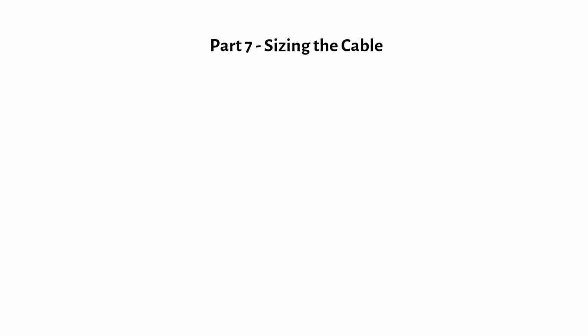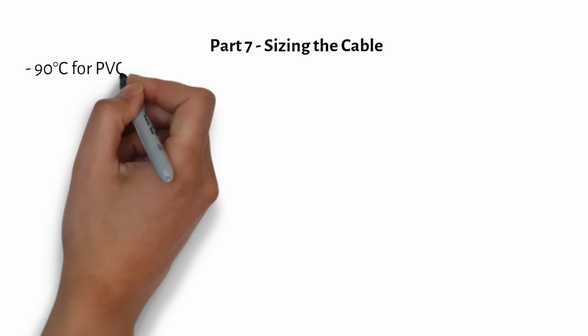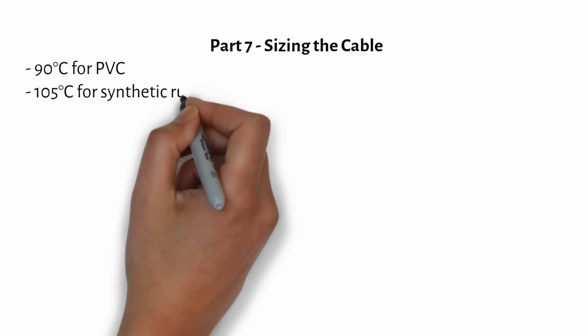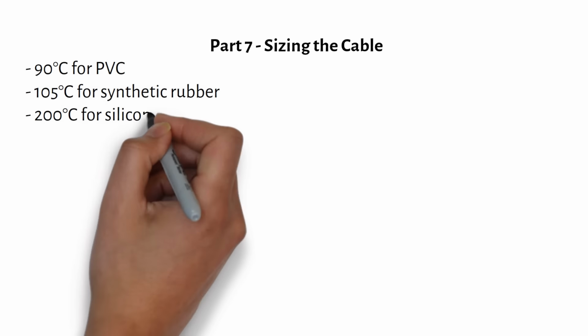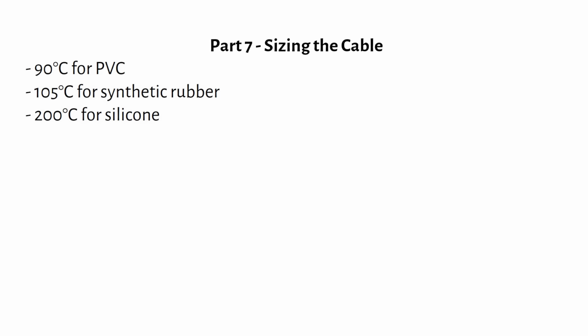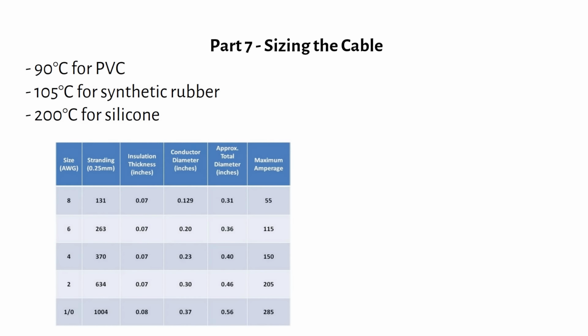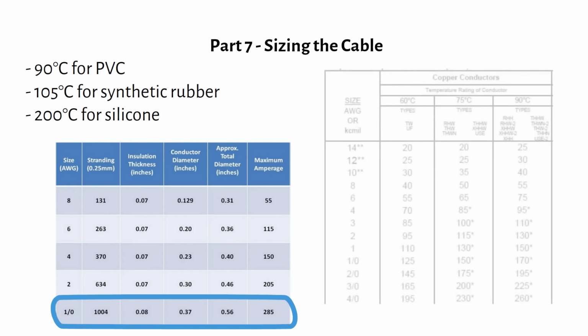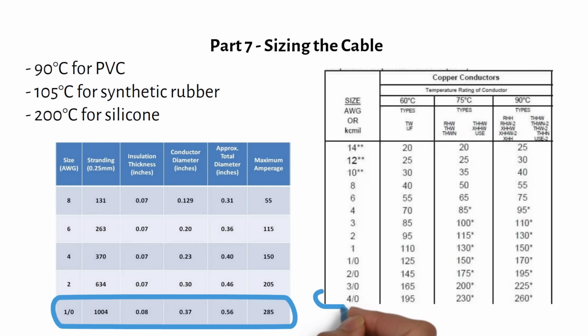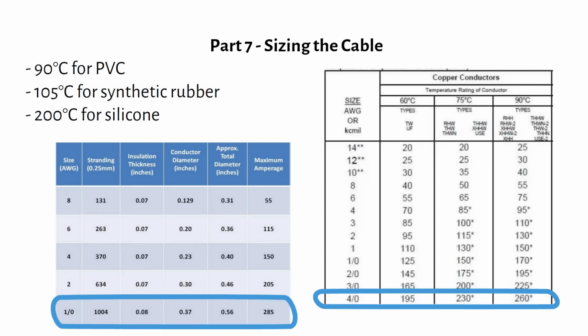Let's size the cable next. That's quite easy. First you pick the temperature rating of your conductor insulation. This can be 90 degrees Celsius for PVC, 105 degrees for synthetic rubber, also called welding cable, or 200 degrees Celsius for silicone insulation. The higher the temperature rating, the higher the current carrying capacity of the cable. So for the 250 amp fuse we chose earlier, we need to find a cable that can carry at least 250 amps. If we choose welding cable, then we need a 1/0 gauge or 50 mm square cable. If you were to choose a cable with 90 degrees Celsius insulation temperature, then you would need a 4/0 or 120 mm square cable. So it's important to know what temperature rating your conductor has. I generally recommend using welding cable or silicone cable.